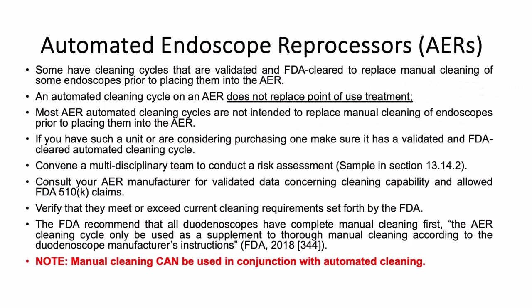Now, automated endoscope reprocessors, or AERs. Some of them have cycles that are validated for cleaning. Now, AAMI says that an automated cleaning cycle does not replace the point-of-use treatment. That has to be done regardless of how the scope is going to be processed. And most AER cleaning cycles are not intended to replace manual cleaning of endoscopes prior to placing them in the AER. Now, I know some people have purchased AERs that have a clearance for automated cleaning.